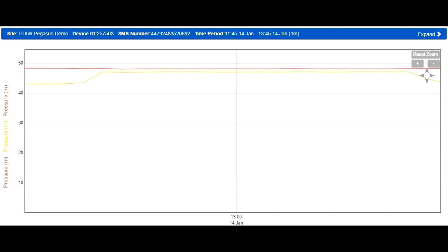After a configurable amount of time, we are able to see, and if you remember, we saw the physical action happening a few minutes ago in this same video, that our yellow line downstream pressure, or outlet pressure, goes from its maximum open, which was given by the pilot, to the real fully open, which is given by the action of Pegasus, venting the upper chamber of the valve to the atmosphere.